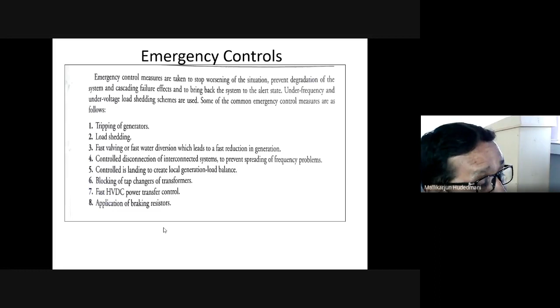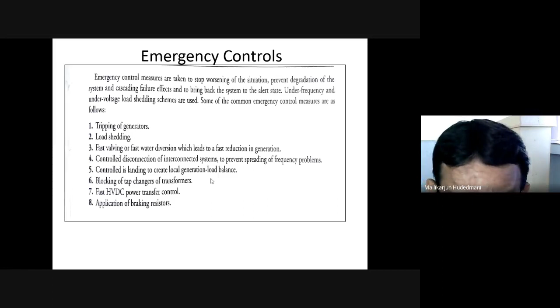Then controlling an islanded area. It means in a disconnection state, when an emergency state results, a wrong set point or wrong control can make the generation setup, sub-transmission setup and distribution center disintegrate. Naturally, they get disconnected, like a natural disaster. Local generation, local balance, local transmission line and disconnection of load, handling the situation in groups, in parts, has to be worked out. That is the controlled islanding to create local generation and load balance.